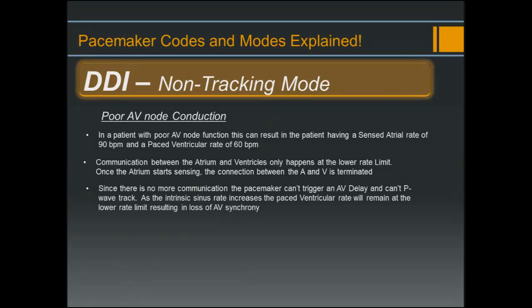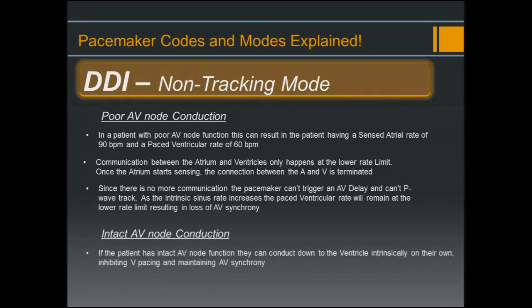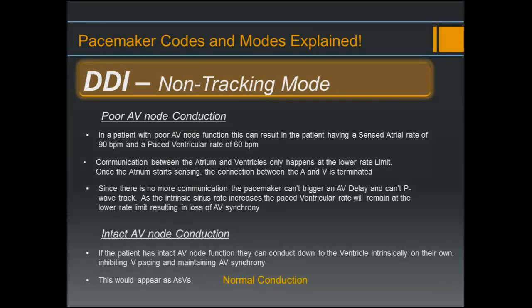The second way DDI plays out is if the patient has intact AV node function — they can conduct down to the ventricle intrinsically on their own, inhibiting V-pacing and maintaining AV synchrony. This would appear as A sense/V sense, or in other words normal conduction.